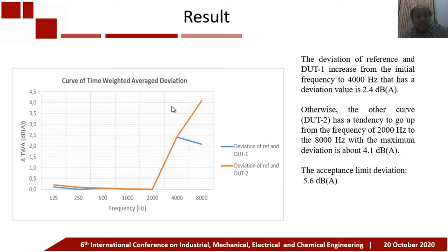And for the optional parameter represented by time weighted average, or TWA, we also obtain the deviation between the standard and DUT, where for DUT1 the maximum value is found at 4 kHz, where the deviation value is 2.4 dB. Meanwhile, for DUT2, the maximum value is found at the frequency of 8 kHz, with a maximum deviation of about 4.1 dB. Meanwhile, the acceptance limit deviation is 5.6 dB. So this value is still acceptable because it is still under the acceptance limit deviation.